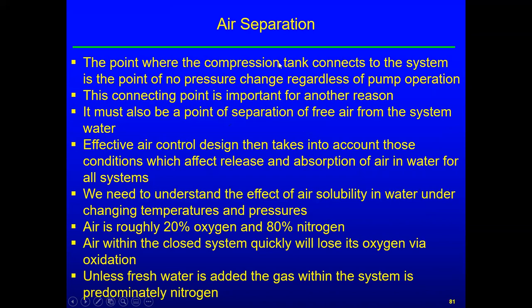Okay. The point where the compression tank connects to the system is the point of no pressure change, regardless of pump operation. This connecting point is important for another reason. It must also be the point of separation of free air from the system water. Effective air control design takes into account these conditions, which affect release and absorption of air in water for all systems. We need to understand the effect of air solubility in water under changing temperatures and pressures.